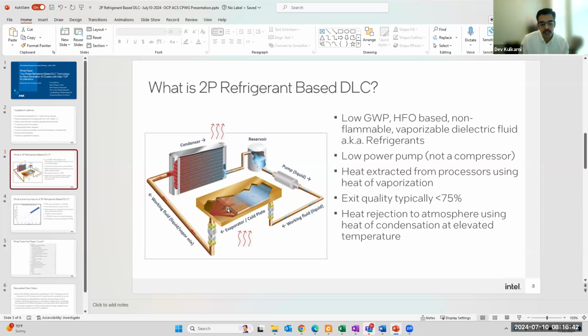And it's also convective boiling. According to the heat transfer correlations, you should get the best thermal performance of any cooling technology, having boiling and forced convection at the same time. The exit quality, as a rule of thumb, is always maintained at 75%, which is 75% vapor going out. So it will always have a vapor-liquid mixture. And for the heat rejection at the CDU side, it could be air or facility water. That is also done by condensation. So from the loop perspective, you get a two-phase phenomenon for the heat extraction and transfer to the ambient. This will give you the best thermal performance in the cooling solution. So that's the high-level working principle.